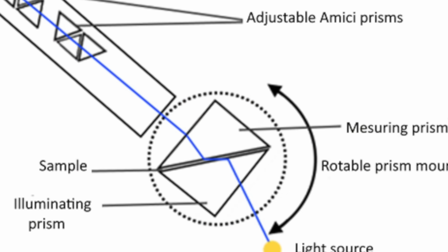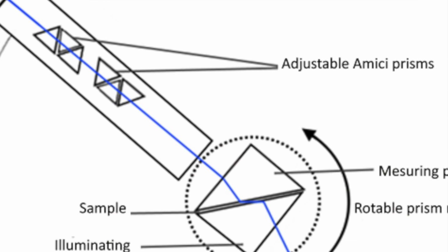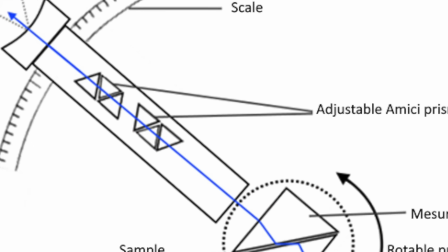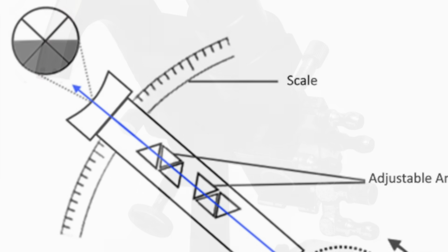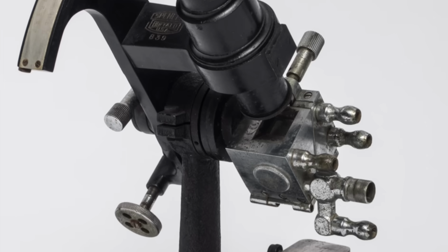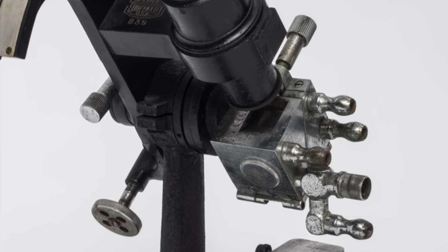Now, refractometer readings are affected by two major factors, temperature and the wavelength of light being used, the effects of which vary from material to material. Abbe's original refractometer used ordinary white light, but featured a set of Amici prisms that could be adjusted to account for the dispersion effects of having this polychromatic light source. Later models used a variety of filters or even sodium lamps to narrow down the wavelengths, whereas modern versions will use, again, filters or LEDs, which can produce very specific wavelengths.